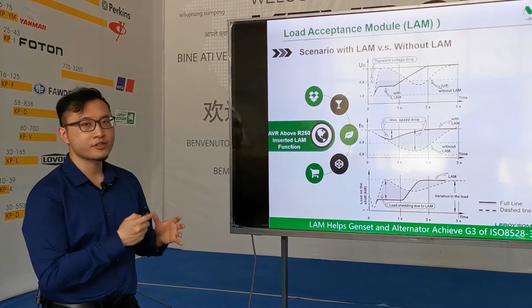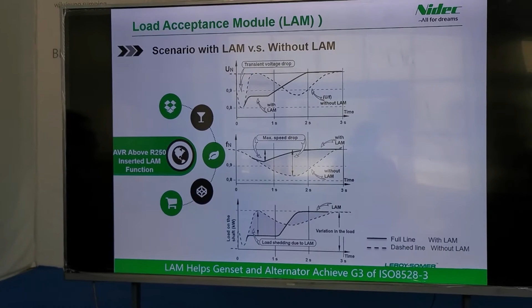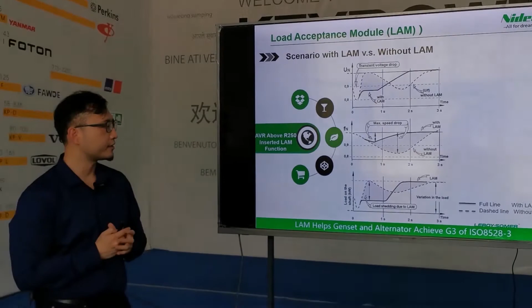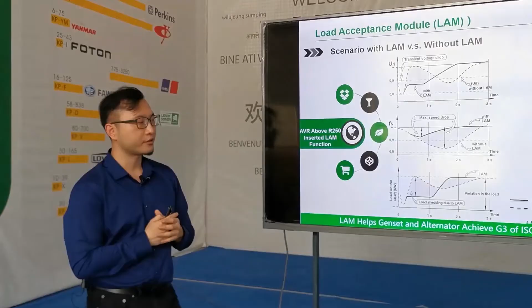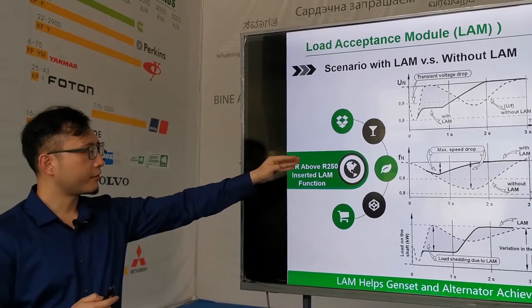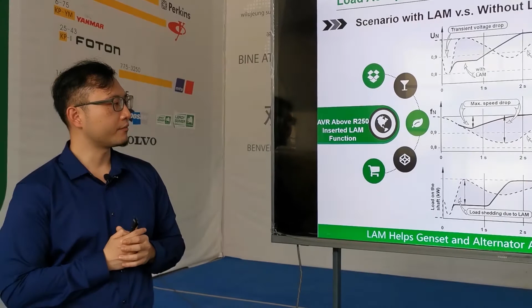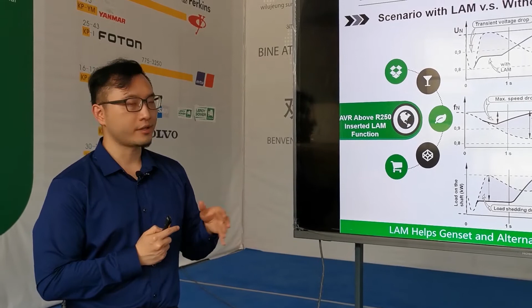And here is a chart to show the difference with LAM and without LAM. You can see that the full line is with the LAM function and the dashed line is without. The first chart is voltage, the second is frequency, and here is load on the shaft. No matter for voltage, frequency or the shaft load, with the LAM function the generator can recover to the rated level smoothly and faster.